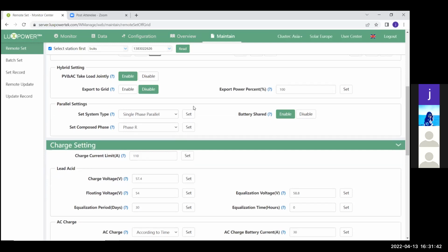Now, the next setting that a lot of people ask me about is the hybrid setting that this off-grid inverter has. This means this inverter has the capability to use your PV power and AC power combined to provide for the loads of your house. So if you have a kilowatt of PV power, but your house is using 1.2 kilowatts, this inverter will take 200 watts from the grid just to fill up that last bit of power that the panels can't provide. And it will use that 200 watts from the grid and not from the batteries, if you enable this setting.